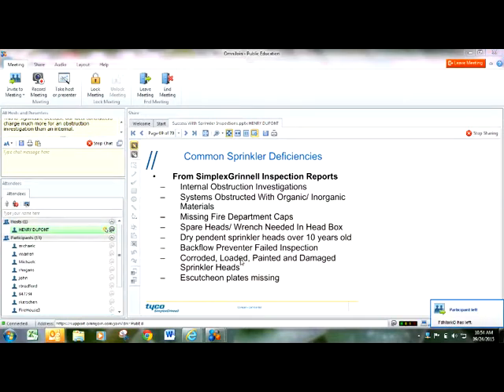Backflow preventers have failed their inspections. Corroded, loaded, and painted sprinkler heads, we see that a lot. And then escutcheon plates missing. The escutcheon plates are required because they are part of the listed device. So a sprinkler head that's in a ceiling without its escutcheon is not a complete listed device.